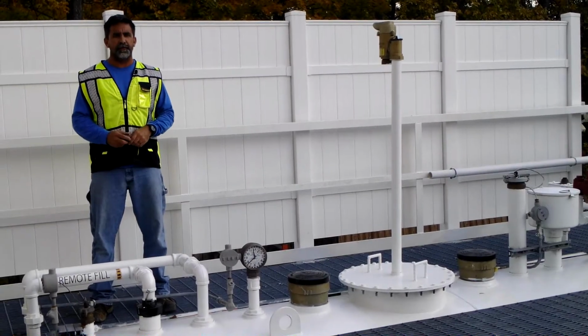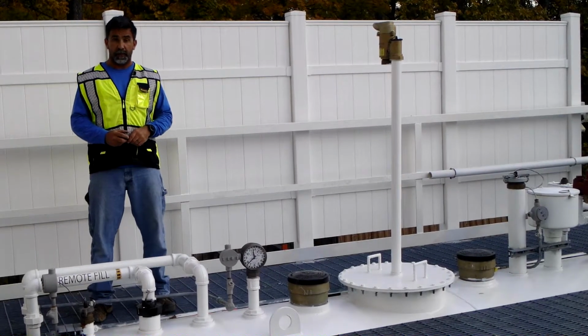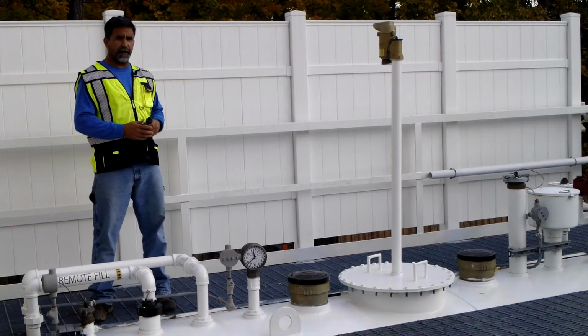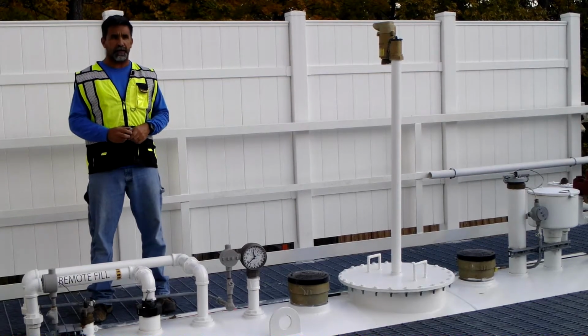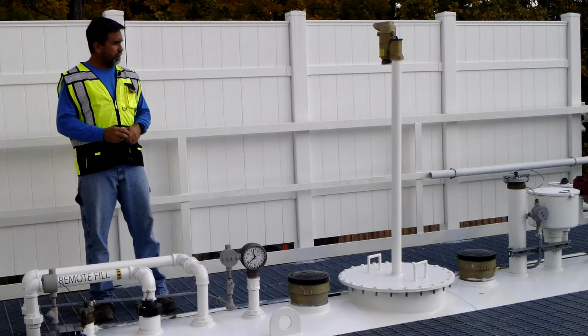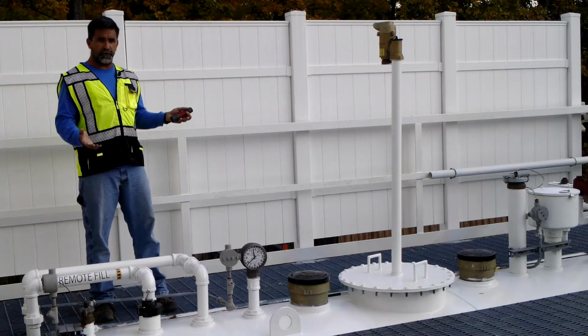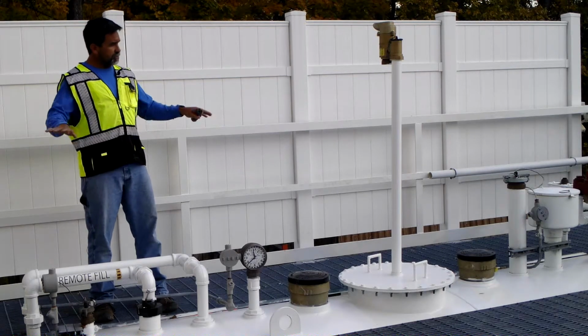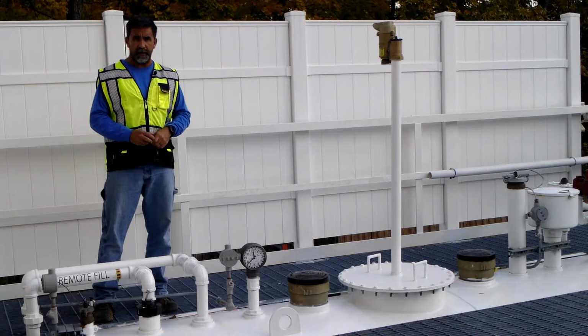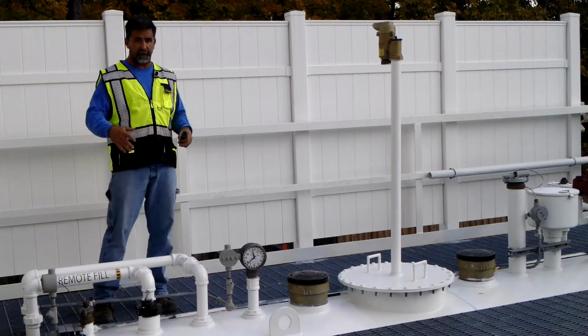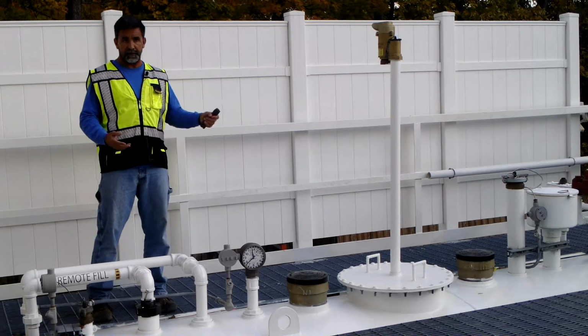Today we will be reviewing how to inspect the interstice of a double wall tank. We are here at MPTI's outdoor training deck. This 5,000 gallon above ground UL 142 double wall steel tank is installed with a safety deck grating around it, which gives us full access to safely inspect and train people on this tank.